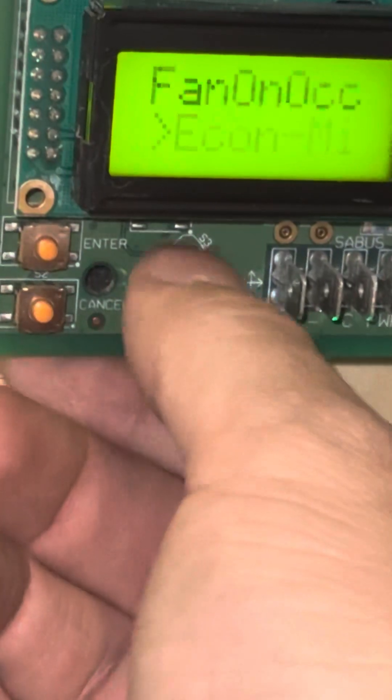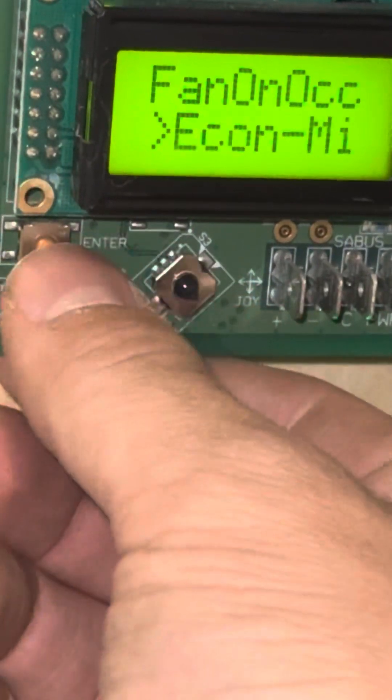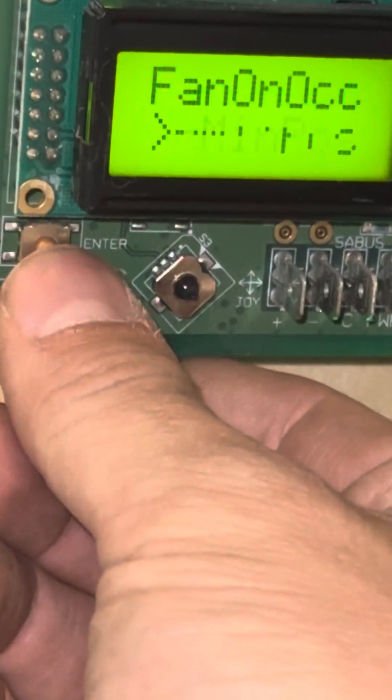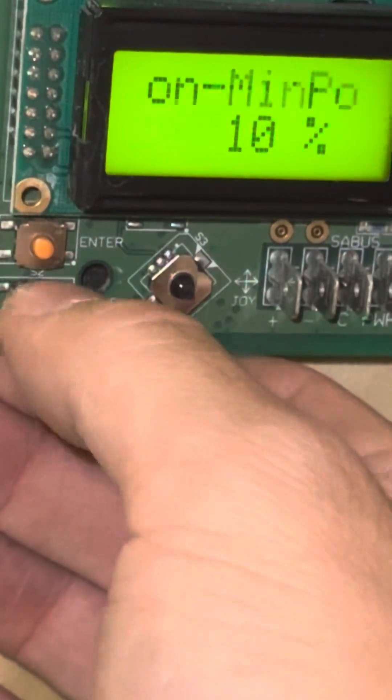Press cancel to go back. Here I can see my economizer minimum position. Again, this minimum position is only for heating and cooling purposes, not when running fan only. That's a different minimum position set point that you set in the economizer menu.